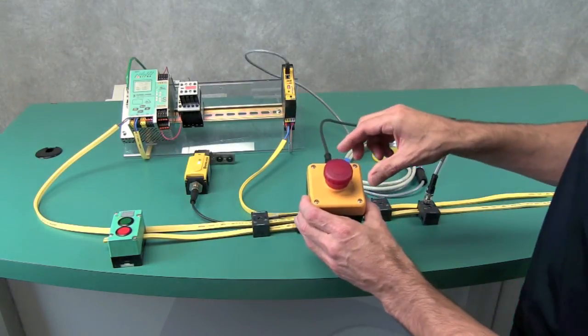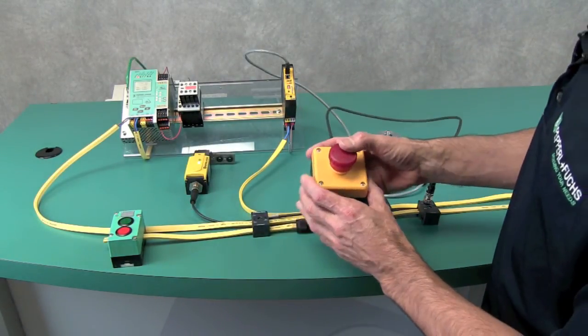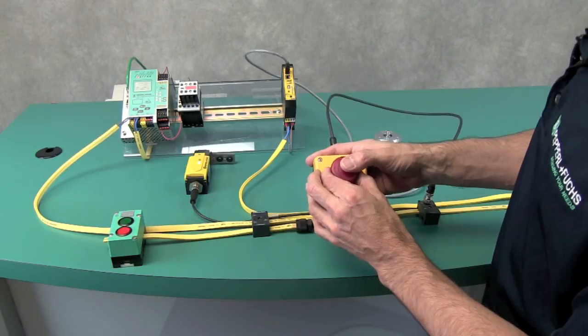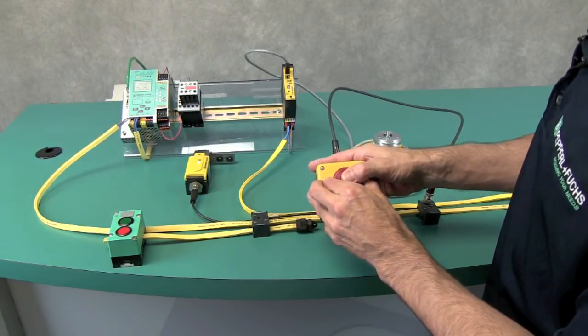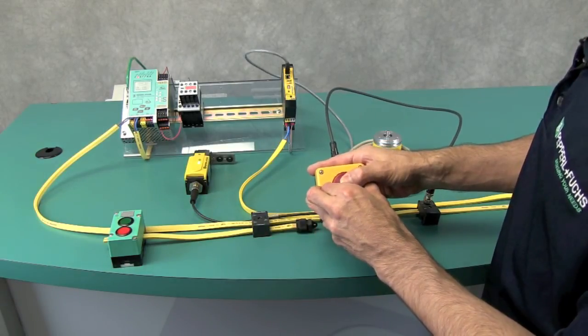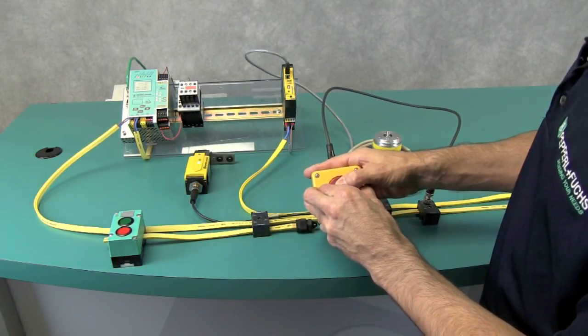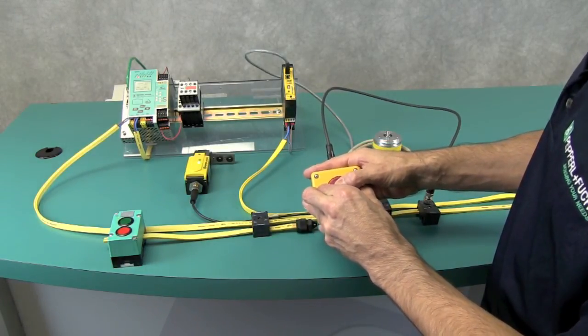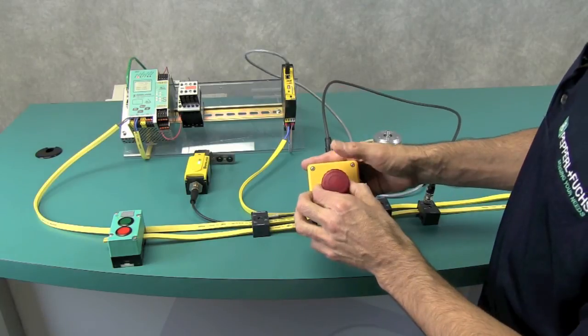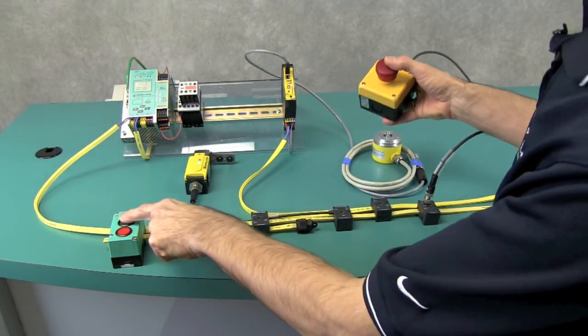I will have to verify that my e-stop does in fact turn off the contactor immediately. And it does. Pulling out the e-stop, I'm allowed to reset the system.